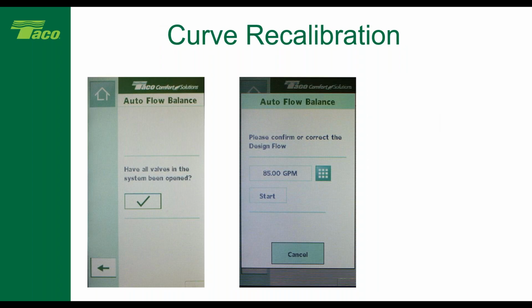So as we talked about, we know that we have, as engineers, we design a system, we do our head loss calculations, and it is our best estimate of what the actual system head loss is going to be. Well, if the mechanical contractor changes the piping a little bit, things get done differently, buys different equipment, maybe that head loss isn't what you thought it was going to be. The reality is when that happens, I have to recalibrate that control curve to match the system as it's actually installed. And this is what autoflow balance is designed to do.